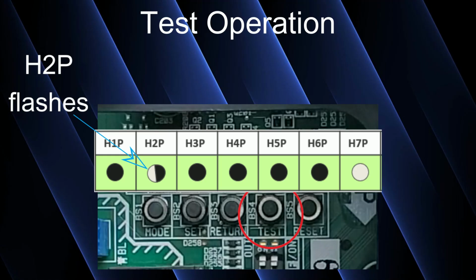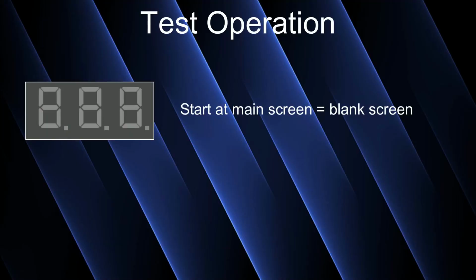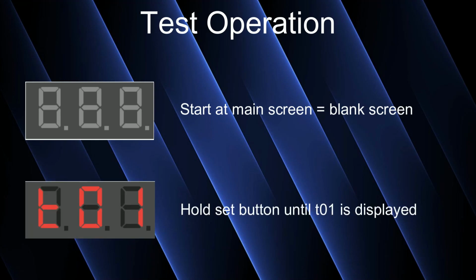The test has begun. On your newer board style, start with the main screen. That's the blank screen. And again, you're going to start the test by pressing and holding the set button. The newer boards do not have a test button, so we're going to hold the set button from a blank screen until we see T01 displayed. That is telling us that now the test has started. Let go of that button.